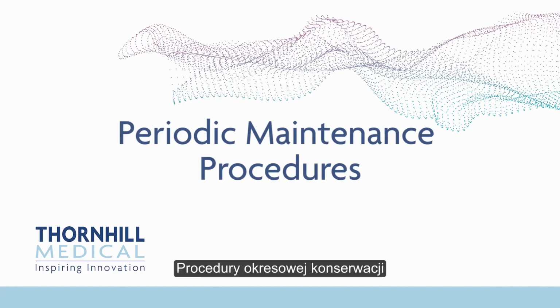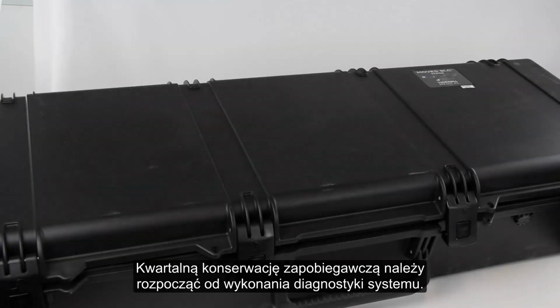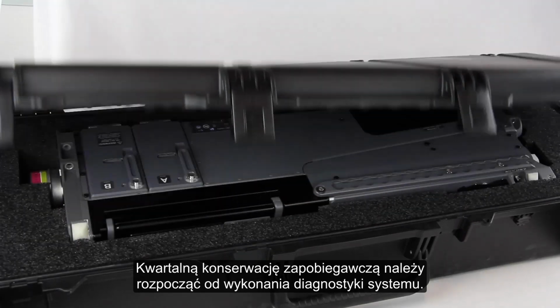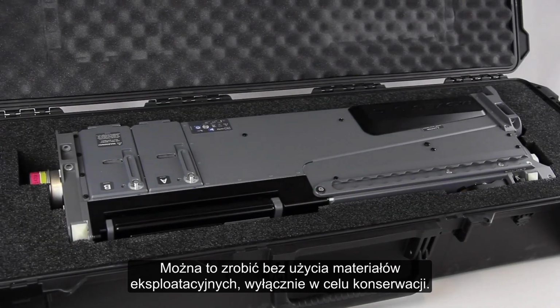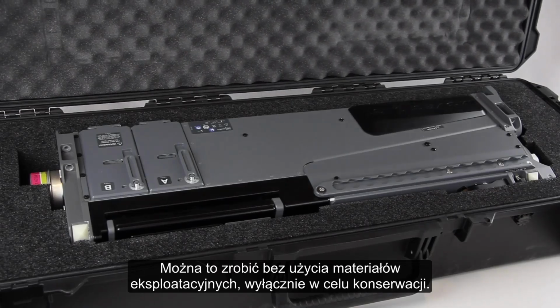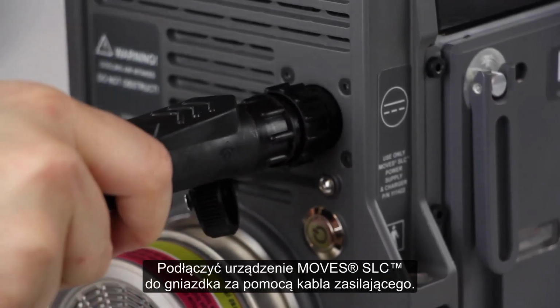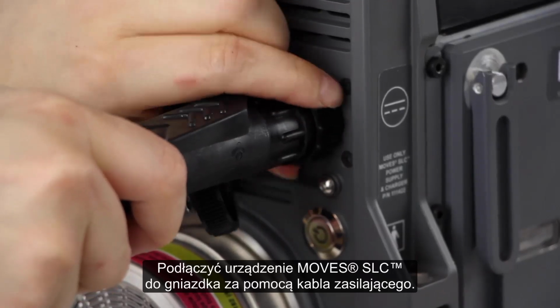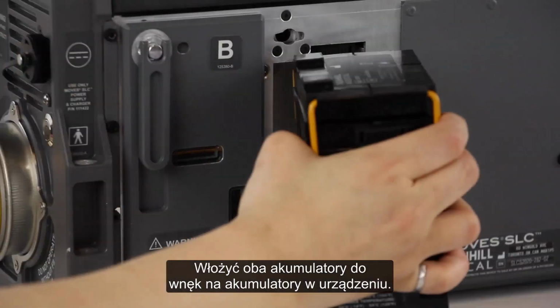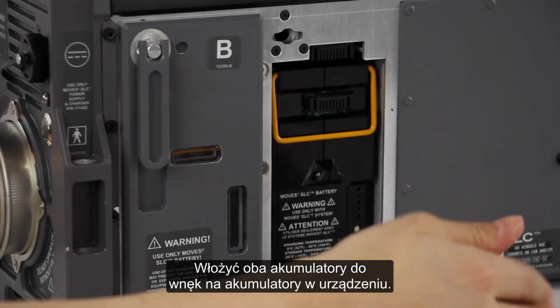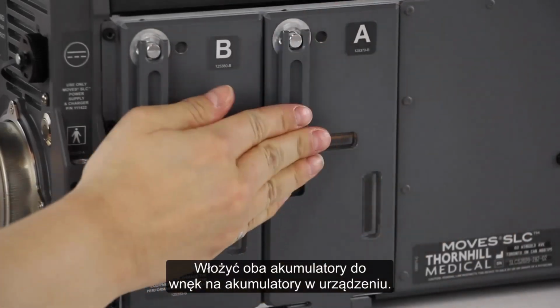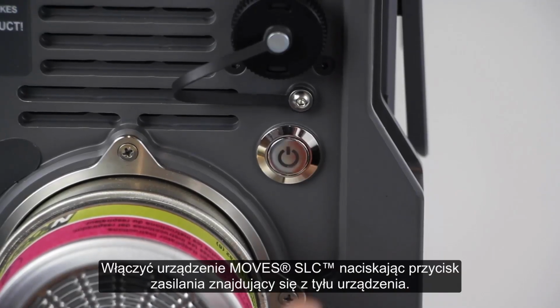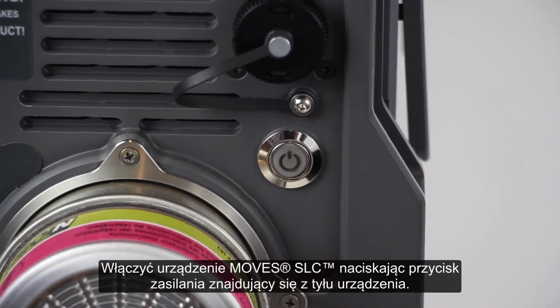Periodic maintenance procedures. Begin quarterly preventative maintenance by completing a system diagnostic. This can be done without the use of consumables for the purpose of maintenance only. Connect Moves SLC to wall power using the power supply. Install both batteries into the battery bays of the device. Turn Moves SLC on by pressing the power button at the rear of the device.